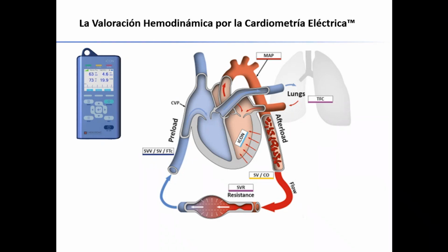Excellent question. So first of all, measurements during, let's say, cardiac surgery, open thorax, are a contraindication. Not so much because the system doesn't work, it works, but with all the fluid changes and maybe even material inside the thorax, we cannot guarantee that the measurements are accurate.